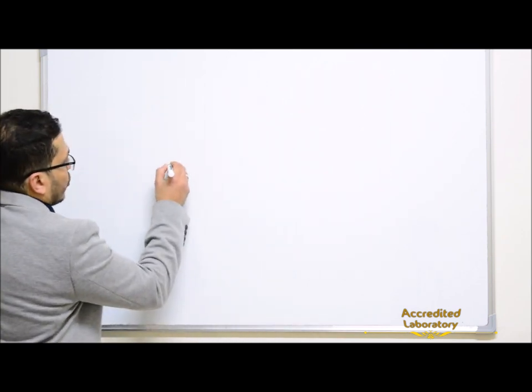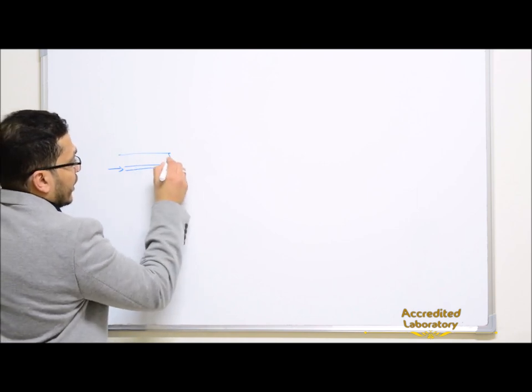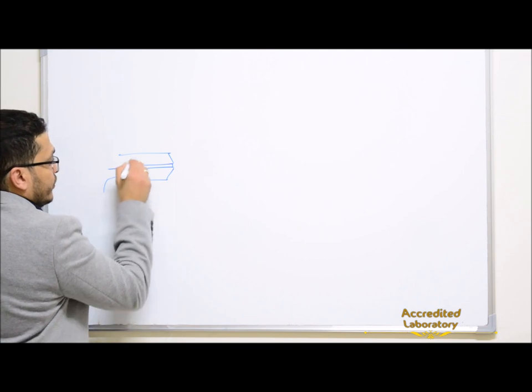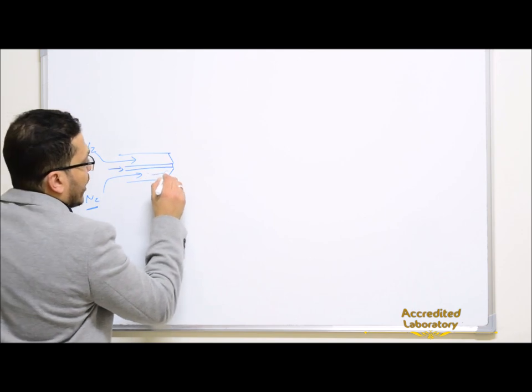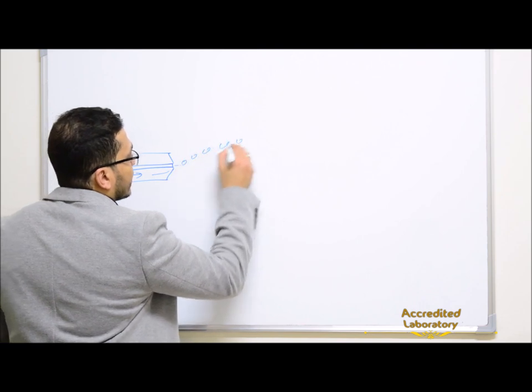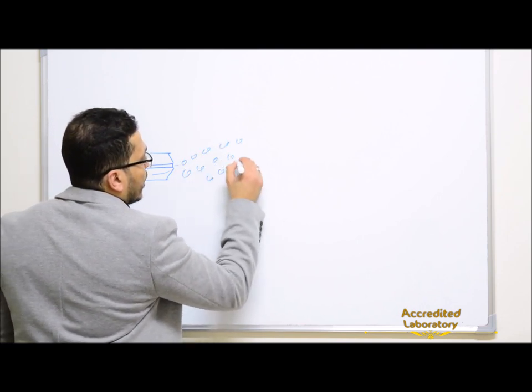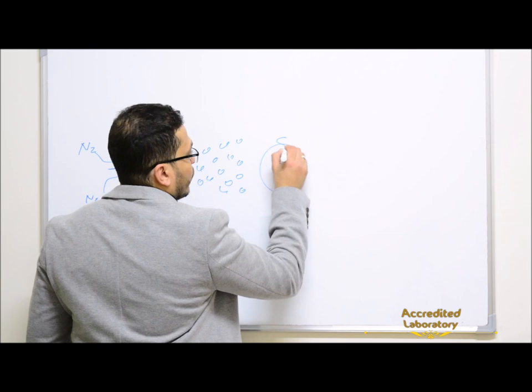In the previous lecture we explained the electrospray ionization ion source, which is the most popular ion source required for most techniques and lab activities nowadays, in which the eluent carrying sample molecules will pass through the needle. Nitrogen nebulizer gas, or sheath gas, will shear around the eluent carrying sample molecules, converting them to spray droplets which consist of sample molecules surrounded by solvent molecules.